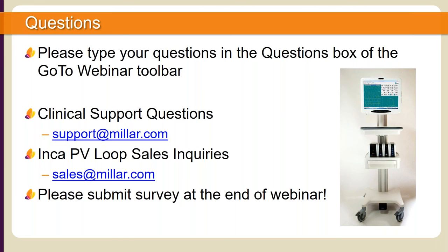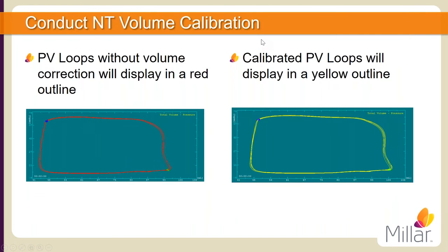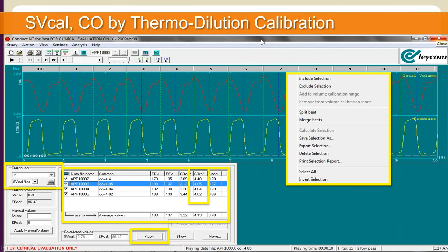Later, when you have time during the experiment, you can go back to analysis and move those data files for the stroke volume determination and for the EF-Cal hypertonic saline to the right boxes. Whenever you assign them directly to SV-Cal files and hypertonic saline files, the program immediately starts calculating, and that will take some time, so you cannot record quickly after that.